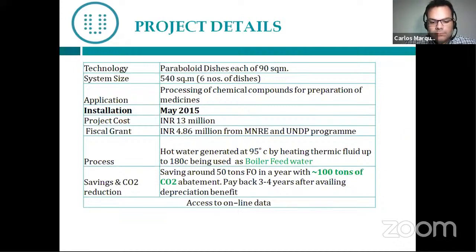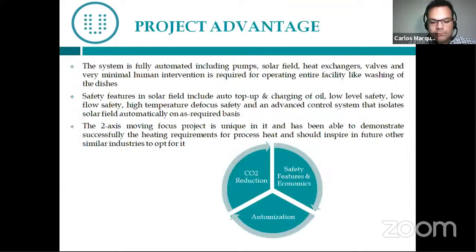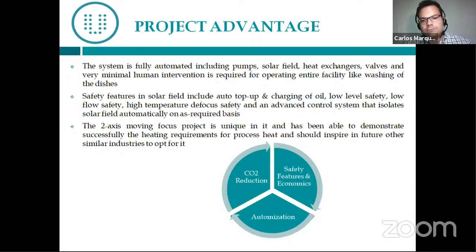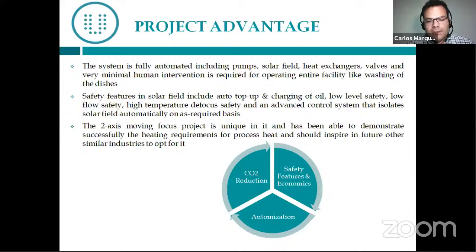The system can give 30 cubic meters of boiler feed water per day at 95 degrees Celsius. Total investment cost is approximately 13 million Indian rupees, with a subsidy of 4.86 million from MNRE and UNDP. This reduces approximately 50 tons of furnace oil and 100 tons of CO2 annually. All data can be accessed online — any process improvement or downtime can be calculated and addressed. The system is completely safe and can synchronize automatically to supply boiler feed water without manual intervention, using solar heating during sunshine hours.